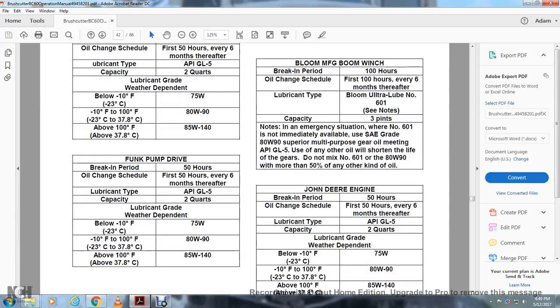Funk pump drive, break-in period 50 hours, oil change schedule 50 hours or every 6 months, whichever comes first. Lubricant API GL5, capacity 2 quarts. Below -10 degrees Fahrenheit, 75 weight. -10 to 100 degrees, 80 to 90 weight. Above 100 degrees, 85 to 140 weight.